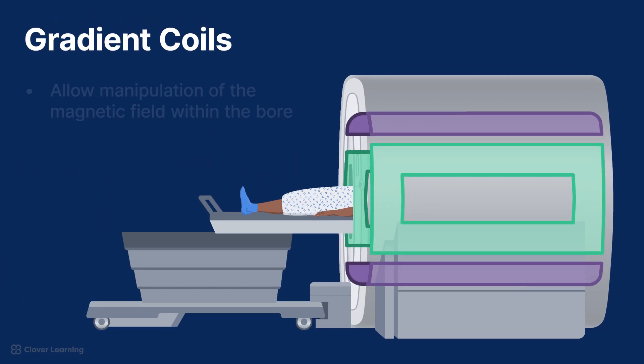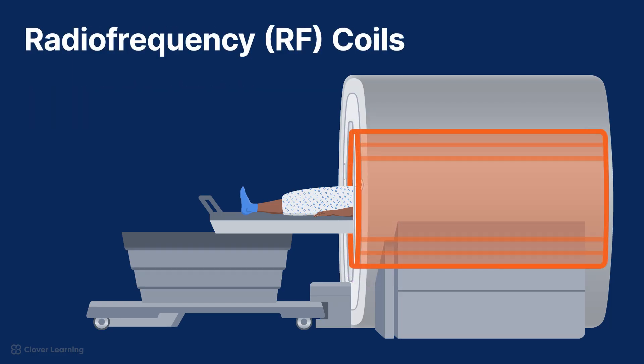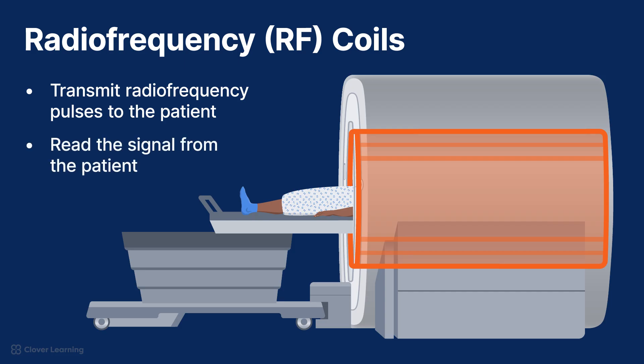The gradient coils in an MRI scanner allow us to manipulate the magnetic field within the bore. Gradient coils modify the magnetic field along different axes or planes, creating variations or gradients in the magnetic field strength across the patient's body. This allows for the MRI scanner to target specific areas of the patient's body for imaging. The radiofrequency, or RF, coils transmit radiofrequency pulses to the patient. There are also RF receive coils that read the signal from the patient. The RF coils are sensitive to signals coming from different areas of the body, which allows for more detailed diagnostic images.